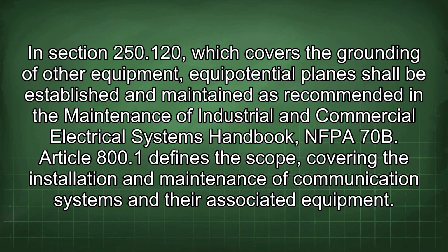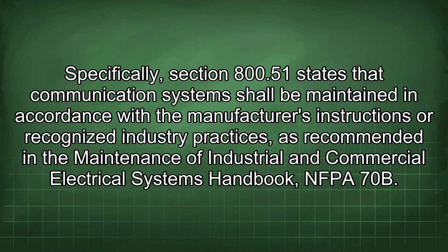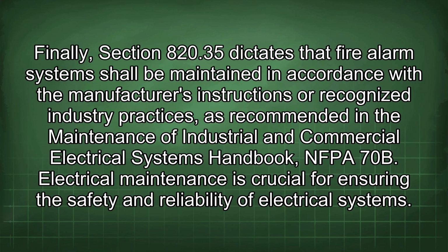Article 800.1 defines the scope covering the installation and maintenance of communication systems and their associated equipment. Specifically, Section 800.51 states that communication systems shall be maintained in accordance with the manufacturer's instructions or recognized industry practices, as recommended in the Maintenance of Industrial and Commercial Electrical Systems Handbook, NFPA 70B. Finally, Section 820.35 dictates that fire alarm systems shall be maintained in accordance with the manufacturer's instructions or recognized industry practices, as recommended in the Maintenance of Industrial and Commercial Electrical Systems Handbook, NFPA 70B.